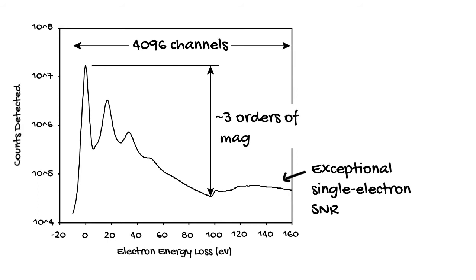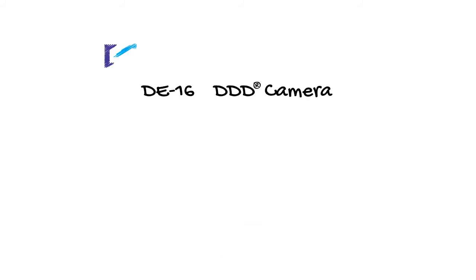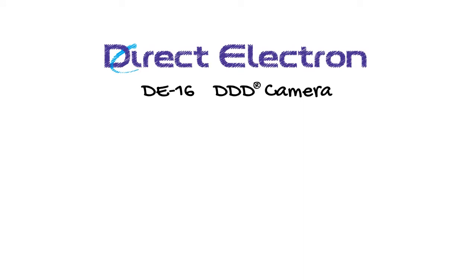Let me introduce you to the DE-16 direct detection camera, built around our 10th generation DDD sensor technology, which is only available from our company, Direct Electron. The DE-16 has 4096 by 4096 pixels, giving you 4K channels for your EEL spectrum. It delivers high signal-to-noise ratio with single-electron sensitivity.